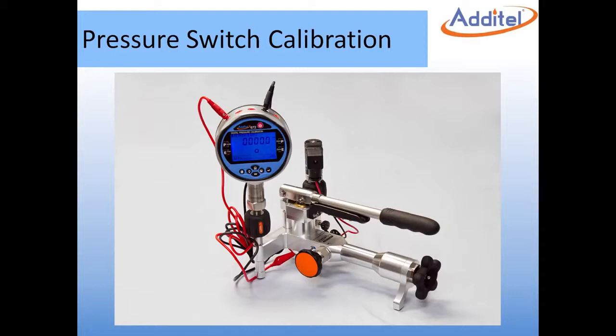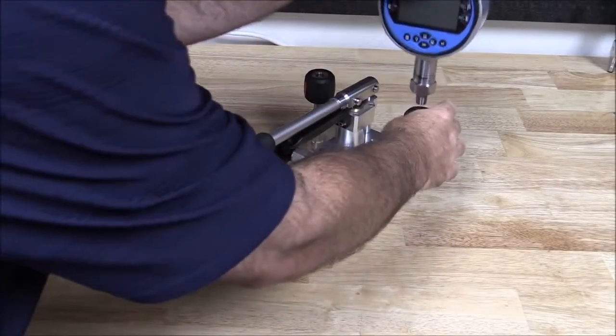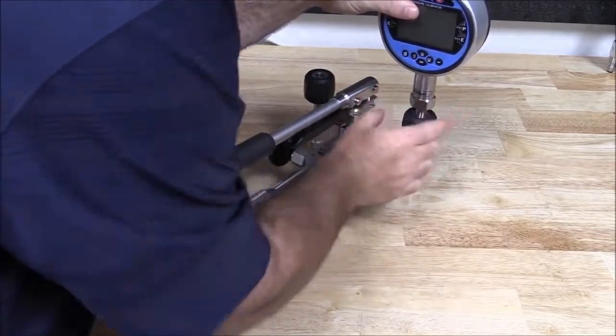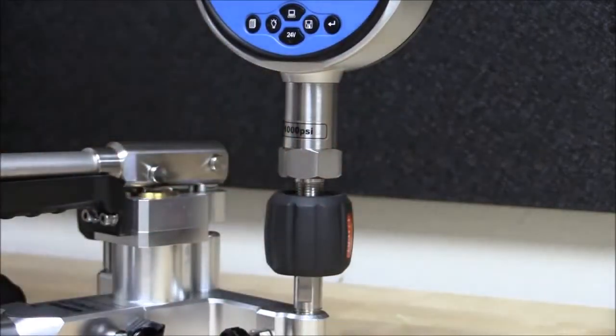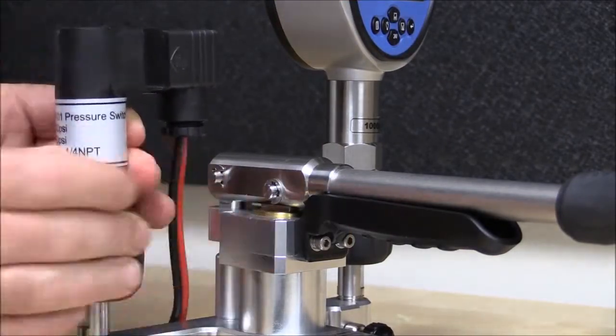In this video, we will demonstrate how to calibrate a 300 psi pressure switch using an Additel Digital Pressure Calibrator and Pneumatic Hand Pump. The Additel 672 Digital Pressure Calibrator and the DUT can be connected directly to the Additel Pump using the hand-tight quick connectors, which do not require the use of PTFE tape or wrenches.